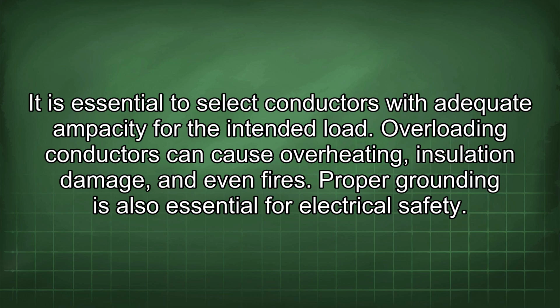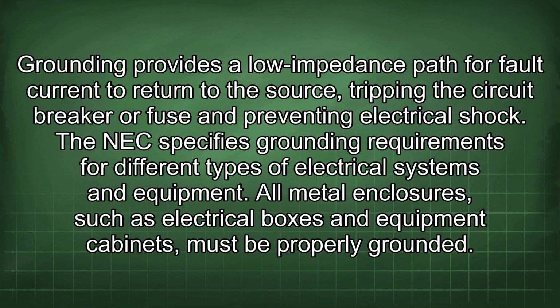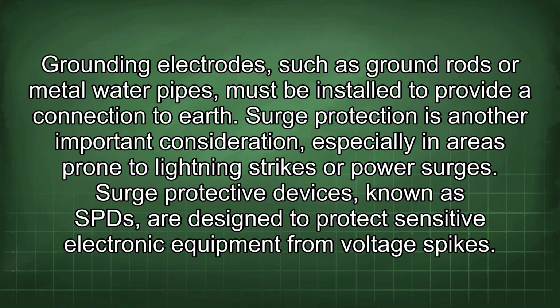Proper grounding is also essential for electrical safety. Grounding provides a low impedance path for fault current to return to the source, tripping the circuit breaker or fuse and preventing electrical shock. The NEC specifies grounding requirements for different types of electrical systems and equipment. All metal enclosures, such as electrical boxes and equipment cabinets, must be properly grounded. Grounding electrodes, such as ground rods or metal water pipes, must be installed to provide a connection to earth.